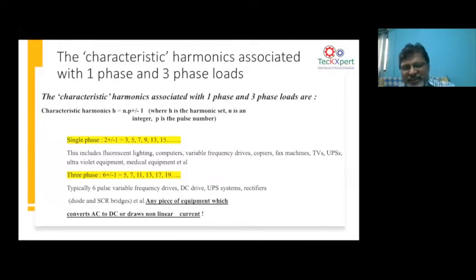We go to the slides later, but when you look into this slide, what you can see is that any power electronic device, whether single phase or three phase, has certain characteristic harmonics created because of the very design of the diodes at the front end of the equipment. When I say front end, the AC power is fed to that device, and when the AC power is coming in, you have diodes sitting there.